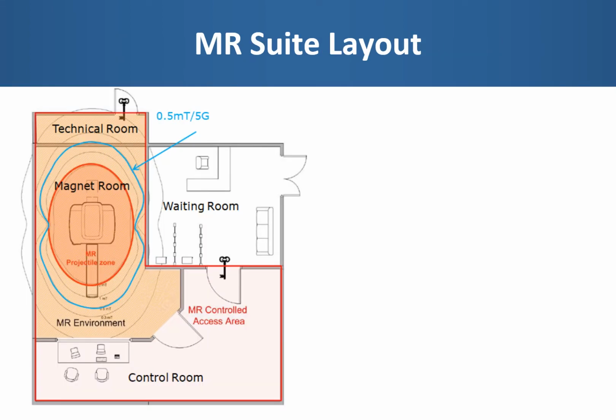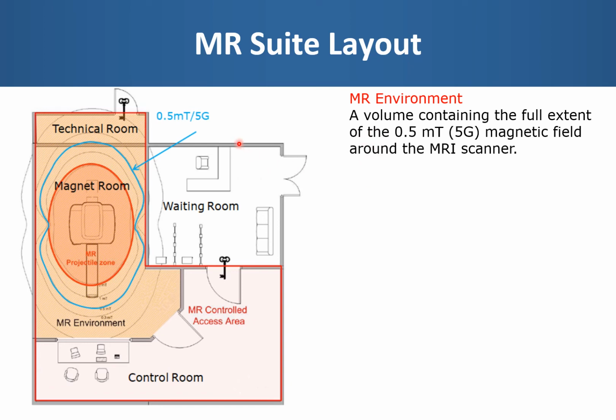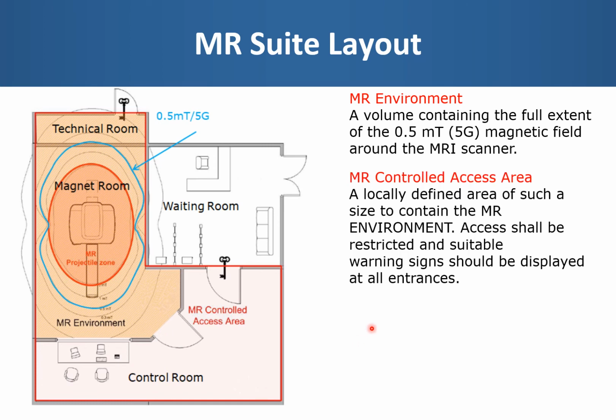In the UK, MRI safety guidance recommends that the MR suite be demarcated by 3 areas. Firstly, the MR environment is a volume, shaded here, that contains the full extent of the 0.5 millitesla magnetic field around the scanner. Note that this volume can extend into other rooms, such as the MR technical room at the back. An MR controlled access area is also defined that contains the MR environment. As the name suggests, the MR controlled access area is restricted and only accessible through the minimum number of self-locking doors, with appropriate warning signs being displayed at all the entrances.